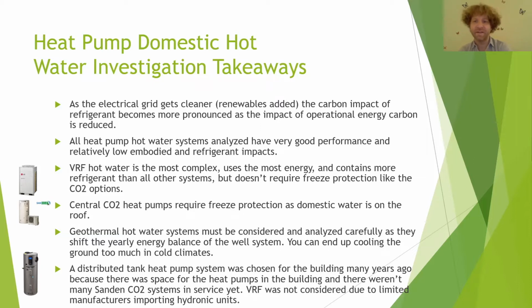I already mentioned the VRF is a bit complex, but it doesn't have any freeze protection issues, because the VRF unit on the roof will never freeze. Whereas all the carbon dioxide based heat pumps put actual water up onto the roof. Normally freeze protection isn't an issue because when the units are on, they manage that themselves, but if you lose power, you have to be careful and provide ways to keep those machines from freezing up on the roof. Distributed tank type hot water heaters don't have that problem either, but you have to figure out how to duct them.